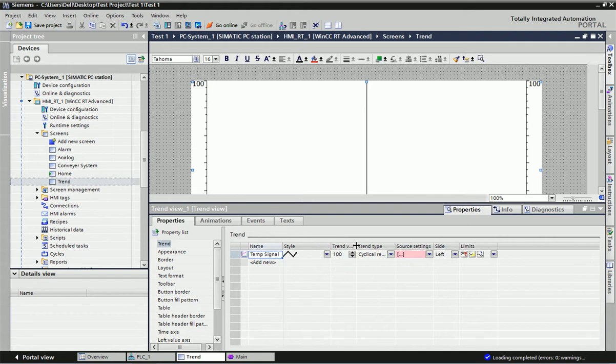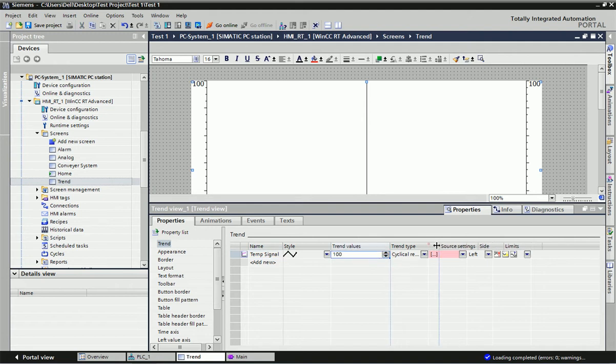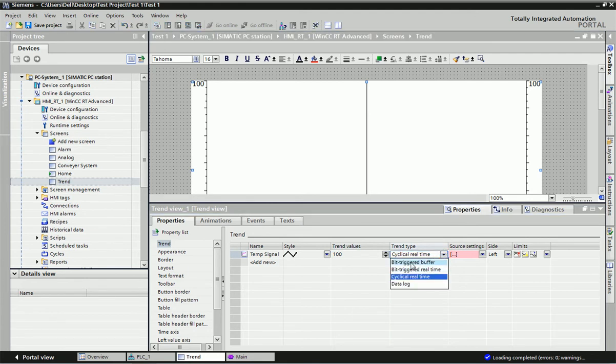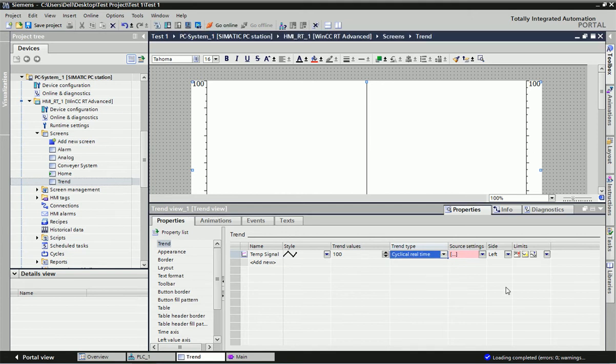You can change the style and the trend values, and set the maximum value. Here we will configure the trend type. There are different types: Bit Triggered Buffer — when a bit triggers, the trend view starts scanning and logging data; Bit Triggered Real Time — starts updating in real time after a bit trigger; Cyclic Real Time — updates data cyclically. If you want historical data, we will go for Data Log, which we will see in the next video. For now, I will select Cyclic Real Time so the analog data updates cyclically.